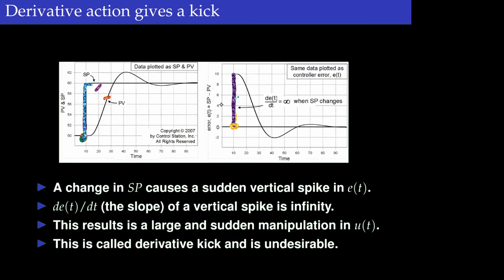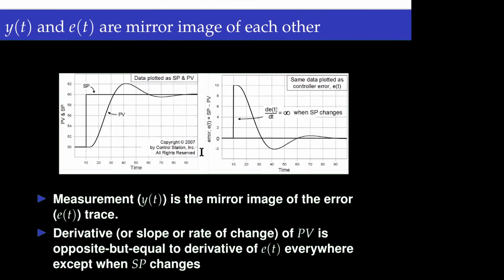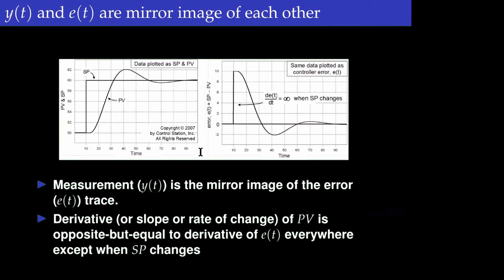From a physical perspective, due to this large derivative action the control valve will either completely open or completely close very fast, causing mechanical wear and tear in the control valve. This is the derivative kick. It occurs because when the set point changes, there is a very large change in the error, so the derivative of that large change gives a very large control action — which is undesirable.